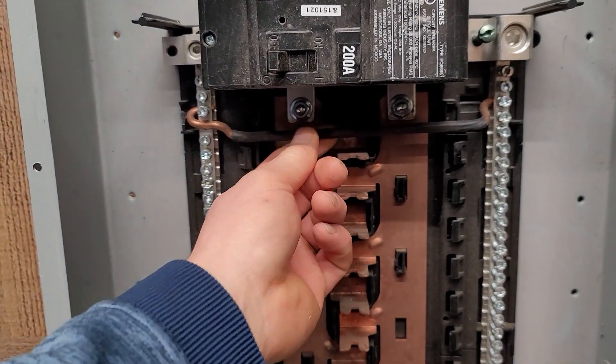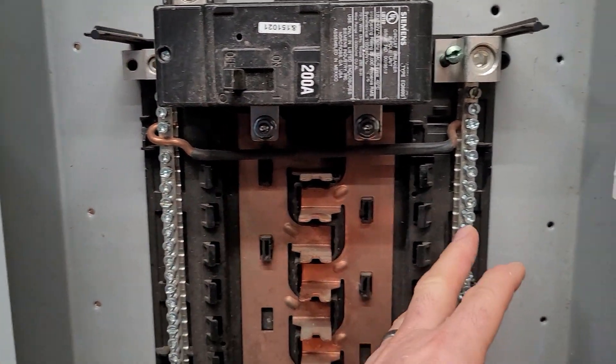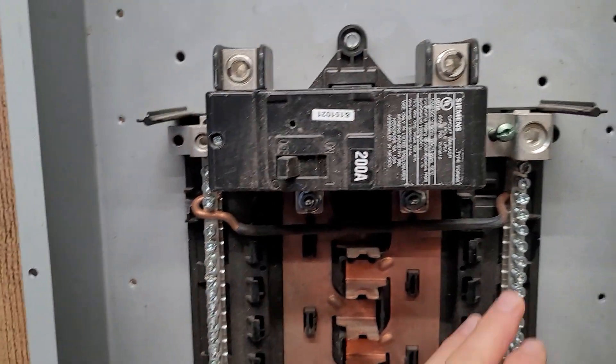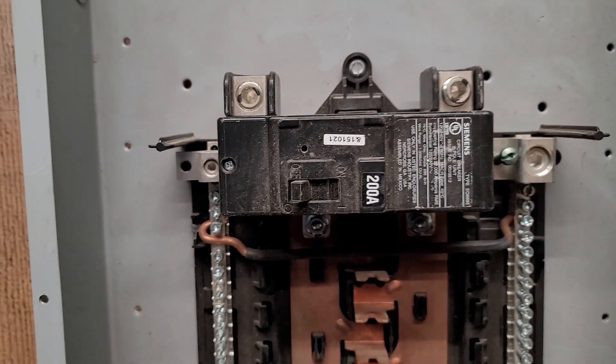But I want to talk about this bar right here. Currently this bar is connecting these two bars right here. So if this were the first point of disconnect I could land grounds and neutrals here. I could land grounds and neutrals here as long as my main bonding jumper was installed and everything else was up to code.